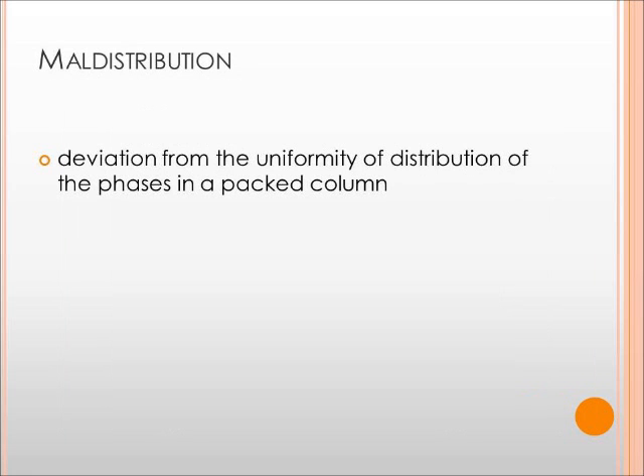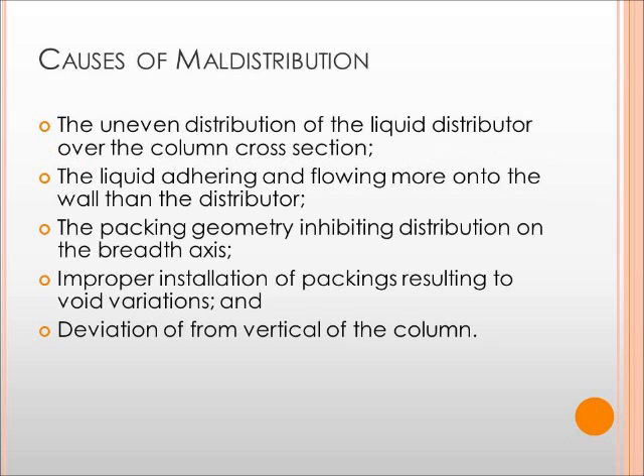Now, any deviation from the uniformity of the distribution over the tower is called maldistribution. There are five main reasons for its occurrence: the uneven distribution of the liquid distributors over the column cross-section, the adherence and flow of liquid onto the walls due to coalescence, inhibition by packing geometry, improper installation of packing materials resulting in void variations, and deviation from the vertical. Like flooding and loading, maldistribution greatly affects the performance of the tower.